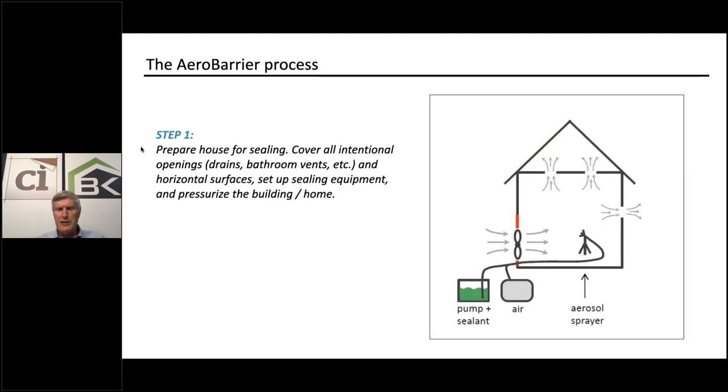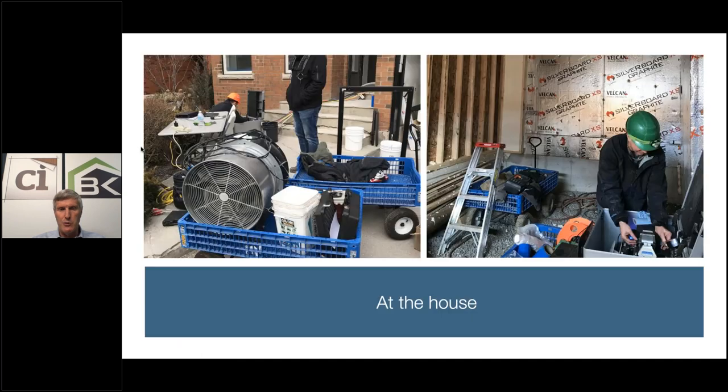Then the process is pretty simple. You prepare the house for sealing. You cover all the intentional openings, drains, bath fans, and so on. You set up the sealing equipment, and you pressurize the building or the home. You're going to be asking me, how long does this take? Well, the pressurization is typically in the order of 100 pascals. Energy raters on this call will recognize that you're testing to 50 pascals. This is twice the pressure, and it's in pressurization mode. So just to give you a sense of order of magnitude, same equipment, but different order of magnitude in terms of the amount of pressurization that we're going to do.